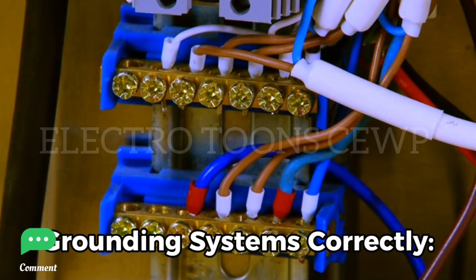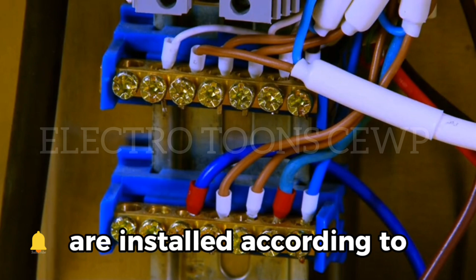How to avoid it? Install grounding systems correctly. Ensure grounding rods, conductors, and electrodes are installed according to code and connected to the electrical panel. Proper bonding: bond all metal parts of the system to prevent differences in potential that could lead to electrical shock.